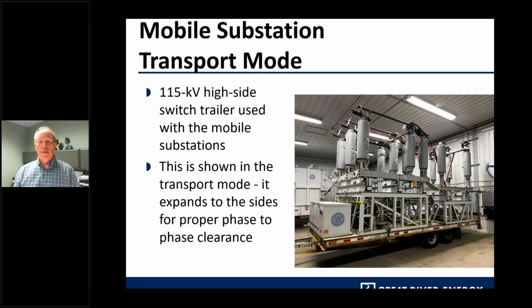Shown here is the 115 kV high side switch trailer used with the 12 MVA mobile sub. When that mobile sub goes in, we first connect from the transmission line down to this switch trailer, and then go from the switch trailer to the high side transformer on the mobile. What you see here is the mobile in transport mode, and those bushings and switches on the top side expand to each side to provide proper phase-to-phase clearance.